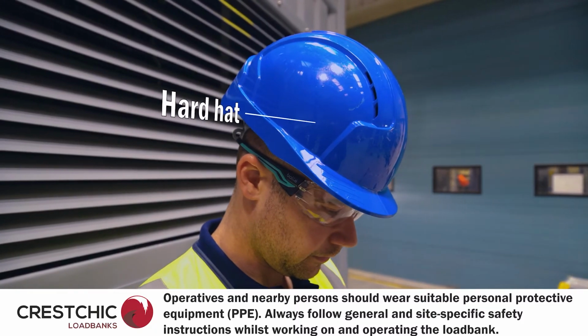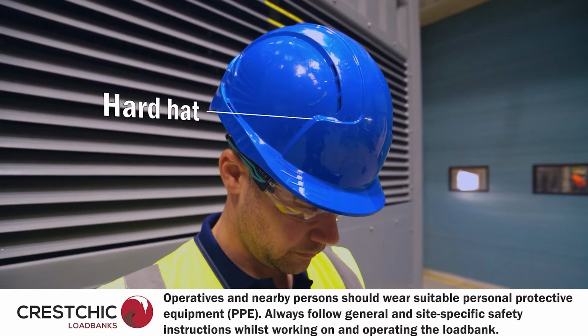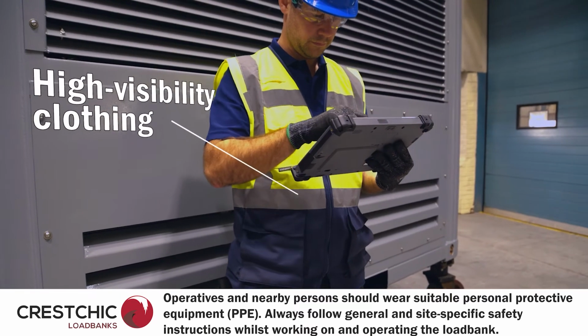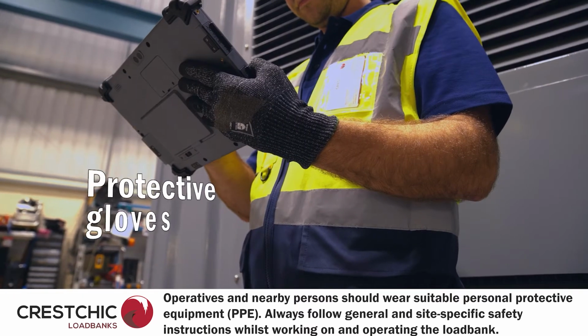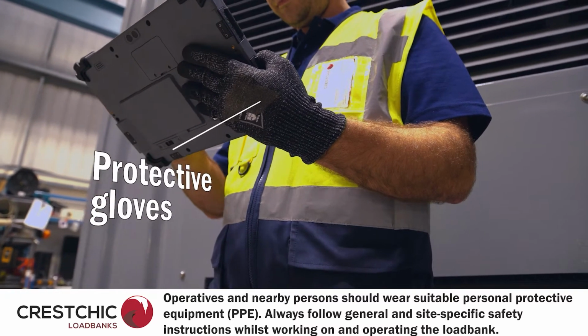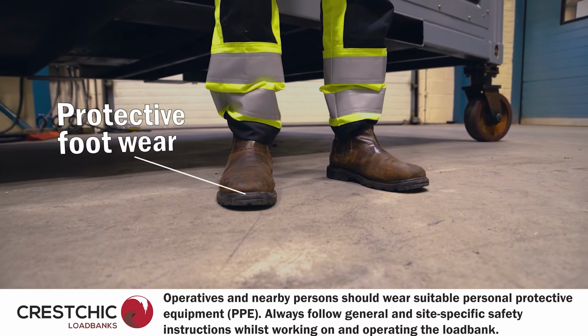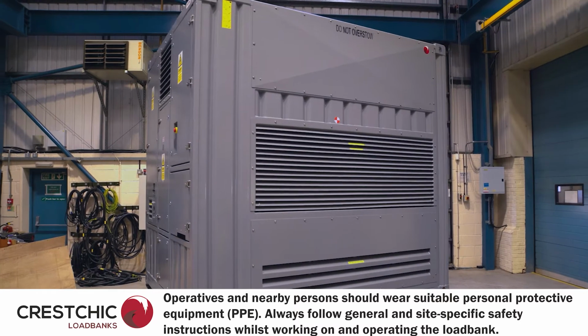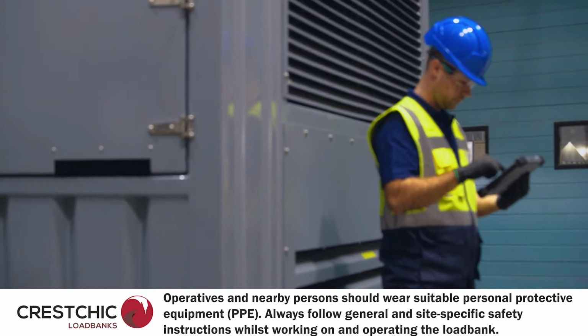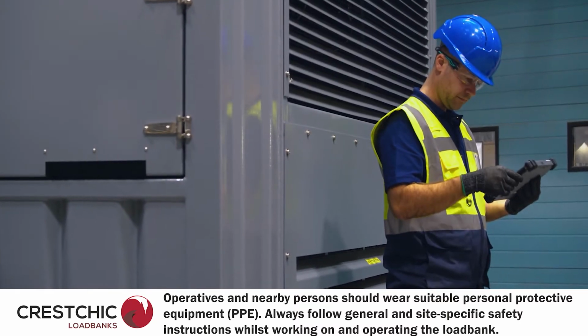Personal protective equipment should be worn by operatives of the load bank and possible nearby persons as an extra measure of safety. An example of this is when the load bank fans are running and persons are nearby to the load bank. Ear protection should be worn to prevent ear damage. General and site-specific safety should be followed at all times.